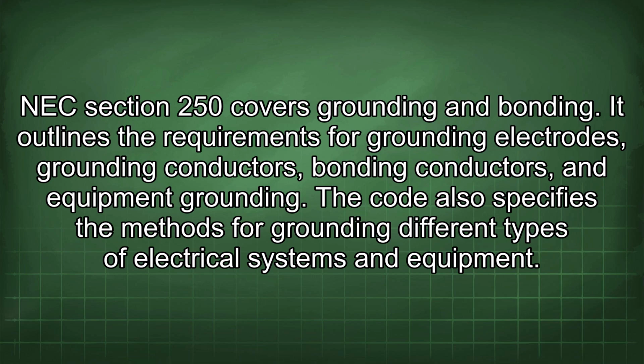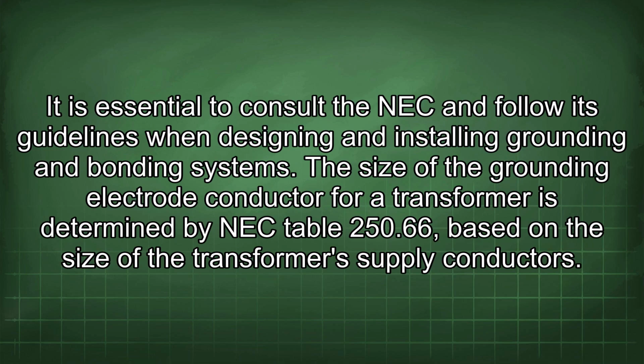NEC Section 250 covers grounding and bonding. It outlines the requirements for grounding electrodes, grounding conductors, bonding conductors, and equipment grounding. The code also specifies the methods for grounding different types of electrical systems and equipment. It is essential to consult the NEC and follow its guidelines when designing and installing grounding and bonding systems. The size of the grounding electrode conductor for a transformer is determined by NEC Table 250.66 based on the size of the transformer's supply conductors.